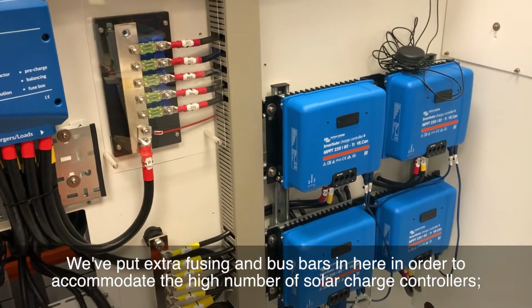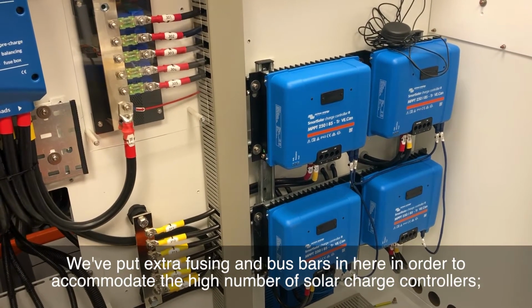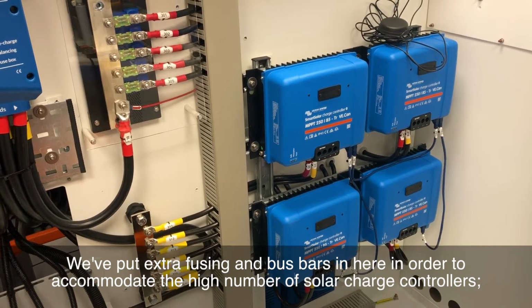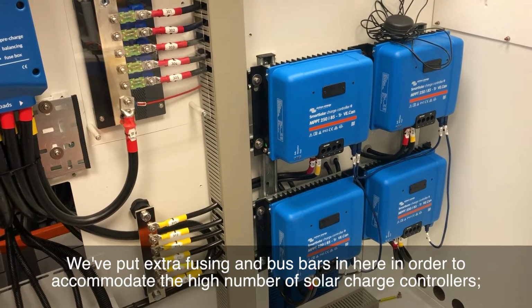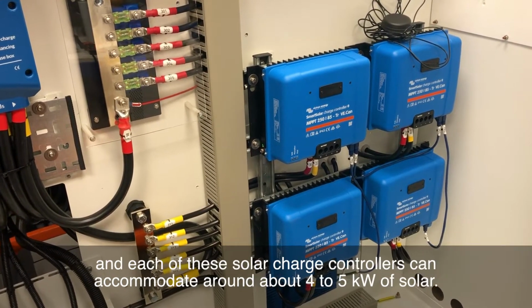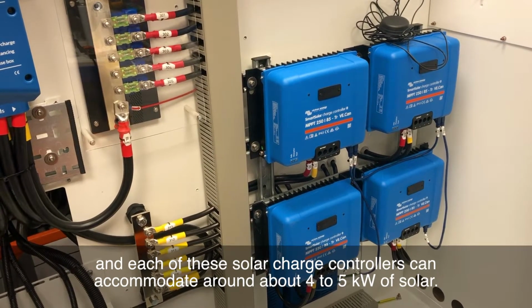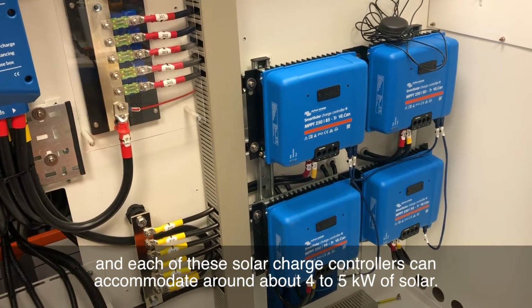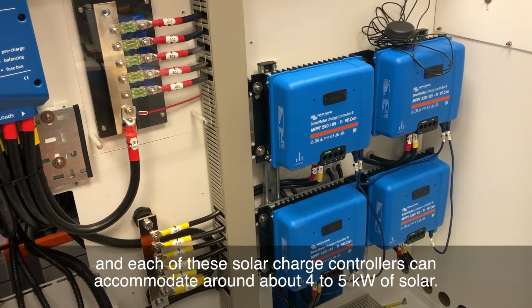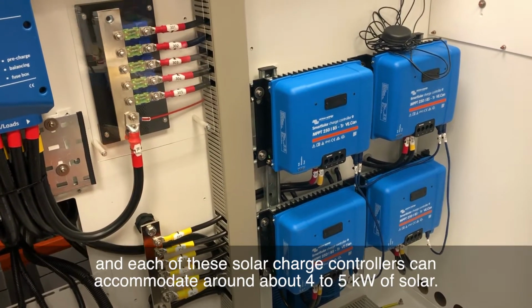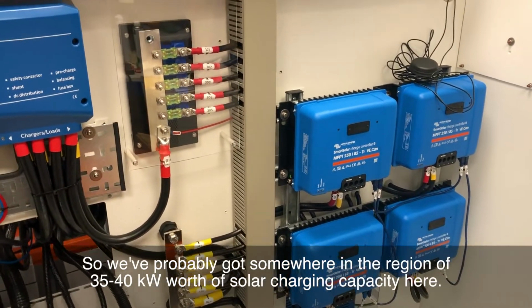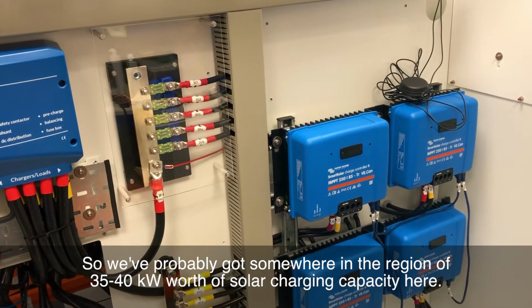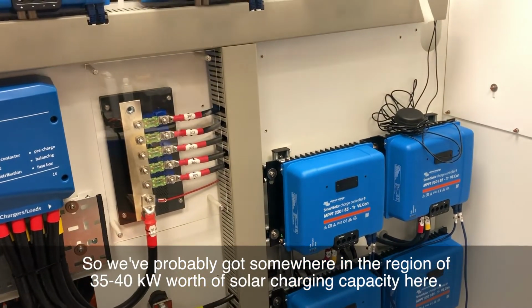We've got extra fusing and bus bars in there to accommodate the high number of solar charge controllers. Each of these controllers can accommodate around 4 or 5 kilowatts worth of solar, so we've probably got somewhere in the region of 35-40 kilowatts worth of solar charging capacity here.